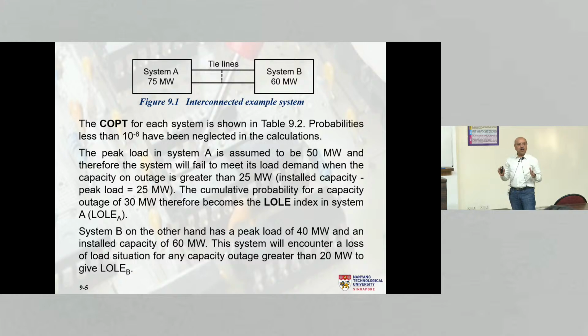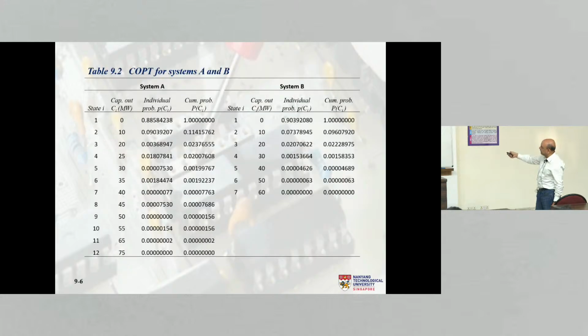Capacity on outage may or may not result in loss of load. But if it is more than 25 megawatt, there is definitely a loss of load, correct? So the cumulative probability for a capacity outage of 30 megawatt therefore becomes the LOLE. So what is the risk in system A? The risk in system A is whenever I cannot supply more than 25 megawatt load, right? So if the capacity outage is 30 or more, then this is the cumulative probability, 0.00199,767. Are you with me?